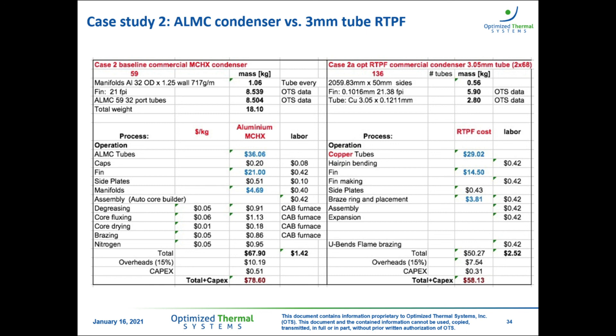The 3 mm copper tube heat exchanger has 0.56 kg sides, 5.9 kg fins, and 2.8 kg tube mass. Main cost contributors are copper tubes at $29.02, fins at $14.50, and braze rings at $3.81. The total for the 3 mm tube heat exchanger is $58.13. This concludes the cost analysis and comparison section.